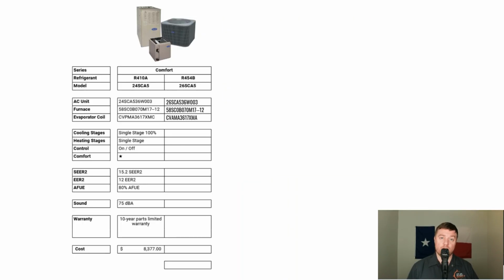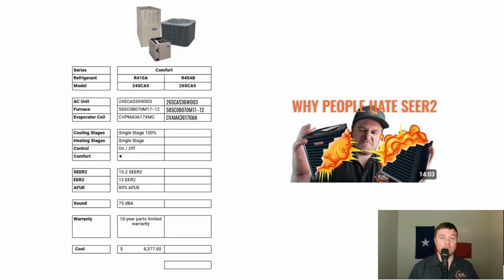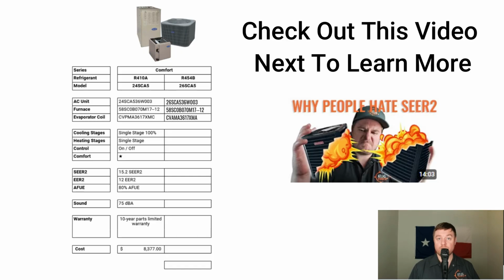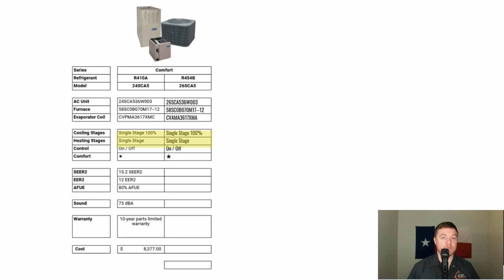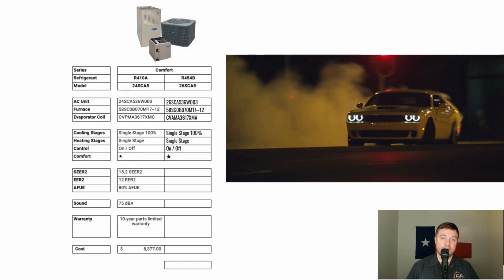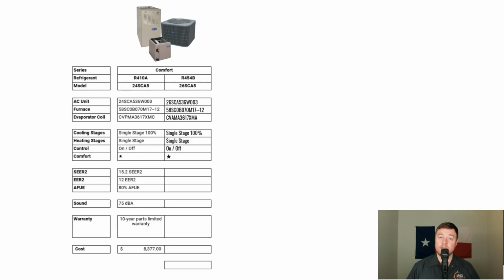That's because Carrier made the bulk of the changes for R454B back when they rolled out the new Series 2 equipment. Now when it comes to the performance of the equipment, both the condenser and furnace are single stage. So it doesn't matter if you're in cooling or heating mode, the equipment only works on or off, at 100% capacity or 0. There's no in between. So you do end up with potential hot and cold spots, along with higher humidity in comparison to the other systems. That's because it's turning on and blasting the air, and then turning right back off. That means the air doesn't cycle all that long in your house, which again could lead to hot and cold spots and humidity issues.